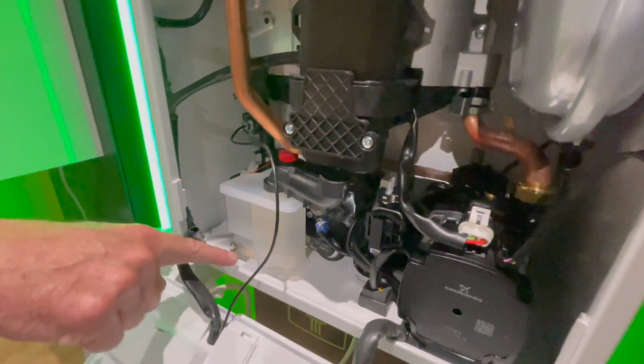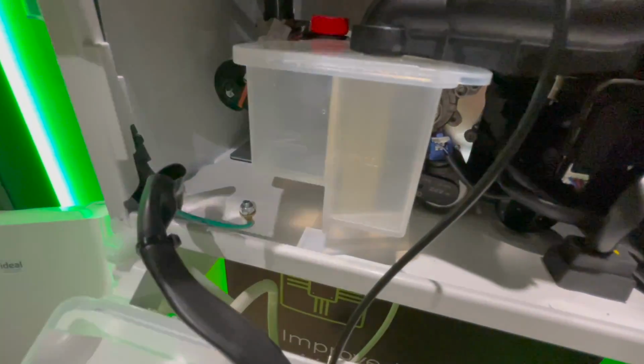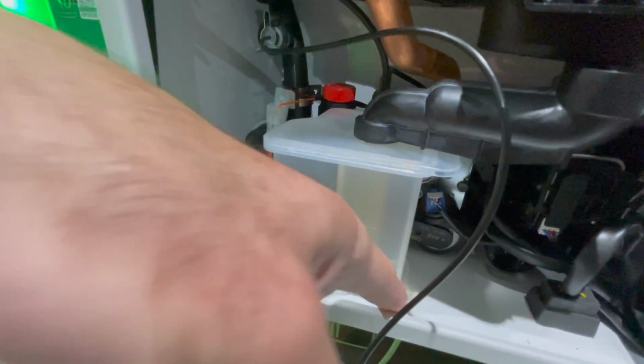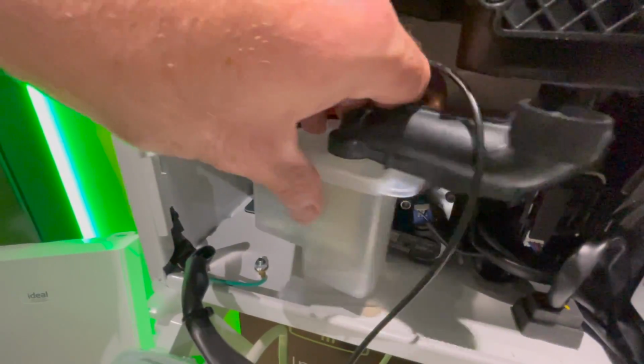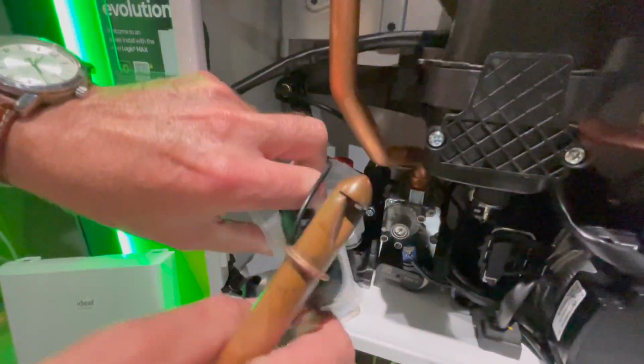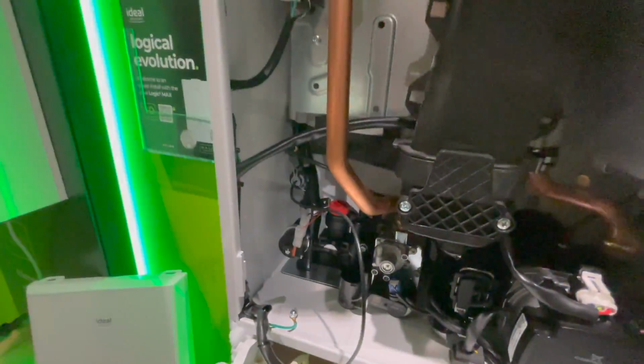That's why there's a new position for the condensate outlet pipe. Now you can also see the casing now is the clamp to hold in the condensate trap. You can see here, if you turn it straight forward, you can't get it out. But if you turn it slightly clockwise, then you can remove it.